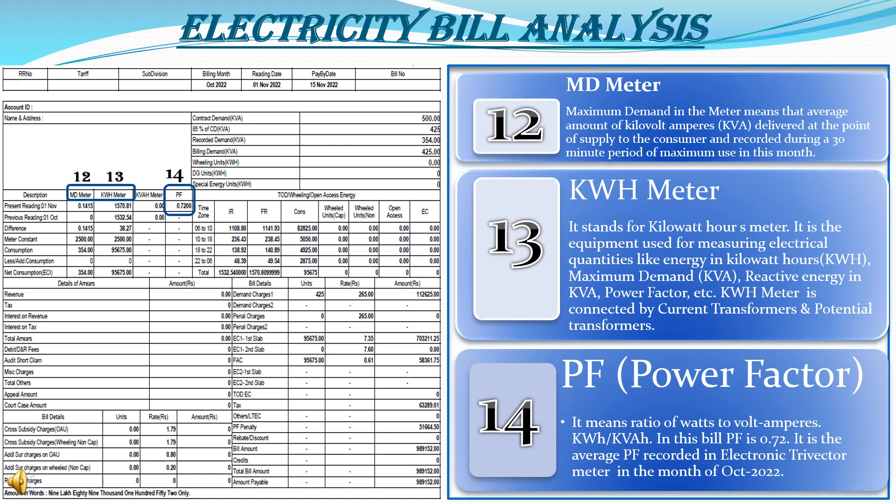MD meter refers to the maximum demand meter — the average amount of KVA delivered at the point of supply to the consumer, recorded during a 30-minute period maximum. This means the consumer utilized a maximum peak load in a duration of 30 minutes from the electricity supply company, which is recorded in the meter. The KWH meter stands for kilowatt hour meter — equipment used for measuring electrical quantities like energy in KWH, maximum demand in KVA, and reactive energy in KVAR.